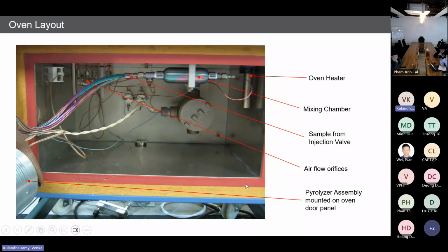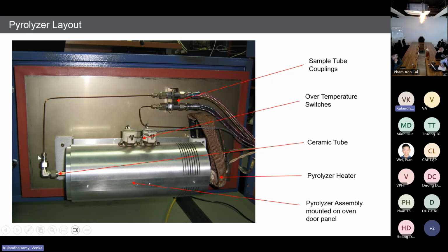Here you can see the oven layout, how it looks physically. Here is the air orifice, which carries the carrier gas, zero gas, to the pyrolyzer. Then the mixing chamber. Here is the oven heater. Then the pyrolyzer assembly is mounted on the door, so it's very easy to do the maintenance. So you are able to reduce the downtime for maintenance. The pyrolyzer assembly is mounted on the oven door.